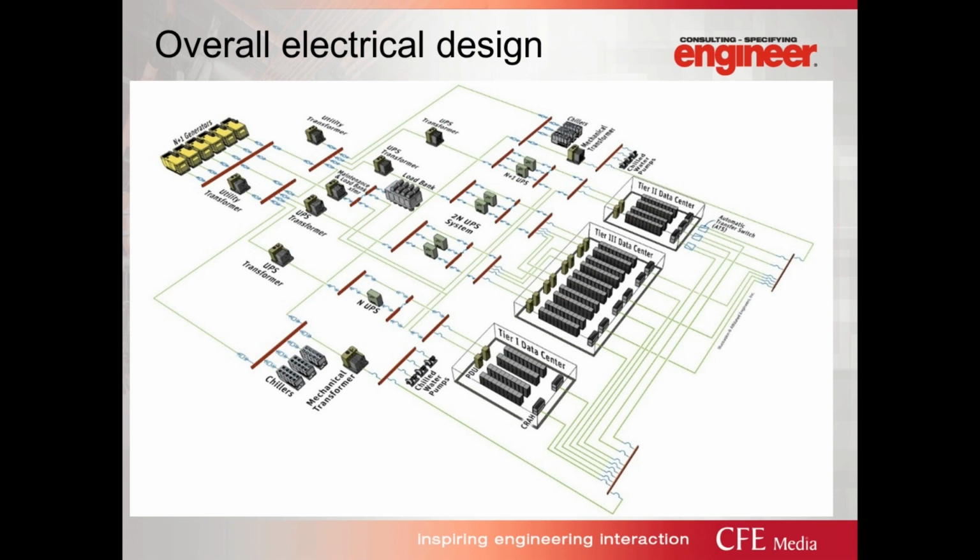Next would be safety. ERMS, arc flash, things like that. How are your operators going to interact with the system? And you need to understand those expectations on the front end of this during schematic design, because if you're talking about remote control panels, manual controls operating from another room, that's real dollars that can add up quickly. And if that's not defined on the front end of this project, budget problems may arise.